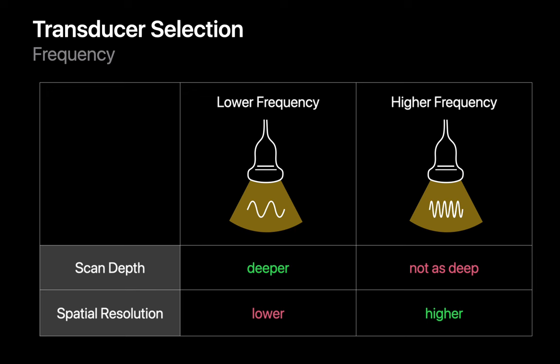Another factor in transducer selection is the frequency of the ultrasound waves emitted by the transducer, which entails a trade-off. Higher frequency ultrasound waves create higher resolution images, but lower frequency ultrasound waves can travel further and permit a greater scan depth. Other factors can also influence penetration depth, such as tissue type — imaging through fat tends to reduce penetration, while imaging through fluid may increase our ability to see deep into the patient.